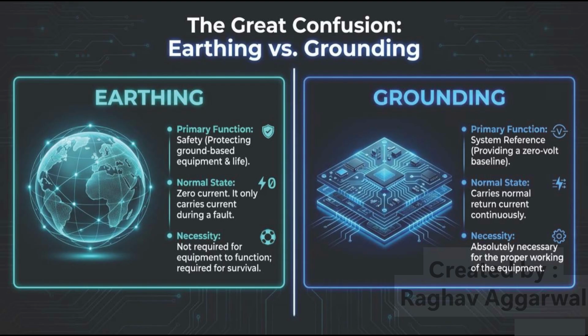Grounding serves a different purpose. Grounding establishes a stable 0-volt reference point for an electrical system. This reference helps equipment operate correctly and consistently. Unlike earthing, grounding normally carries return current as part of standard system operation. Because of this, grounding is essential for proper equipment performance. We need to understand a practical distinction. A piece of equipment may technically operate without earthing, but doing so would be unsafe. Grounding, on the other hand, is necessary for correct system operation.